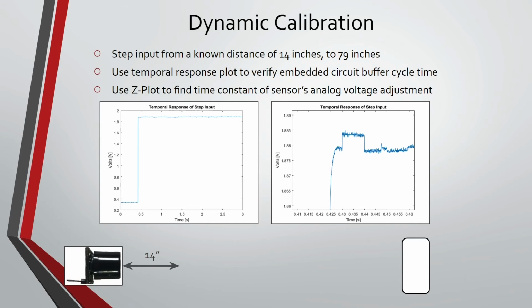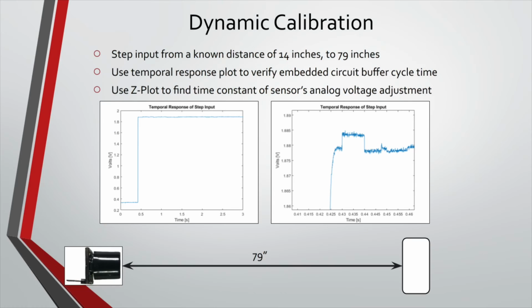Our dynamic calibration results show how a digital sensor such as this can be modeled as a zeroth order system. As this sensor operates on a 50 millisecond cycle and only adjusts its analog output during the last 5 milliseconds of the cycle, the time constant found was that of the analog voltage adjustment circuitry, and thus has no meaningful relationship to the overall bandwidth of the sensor. Rather, the bandwidth of this sensor is determined by the cycle time alone.